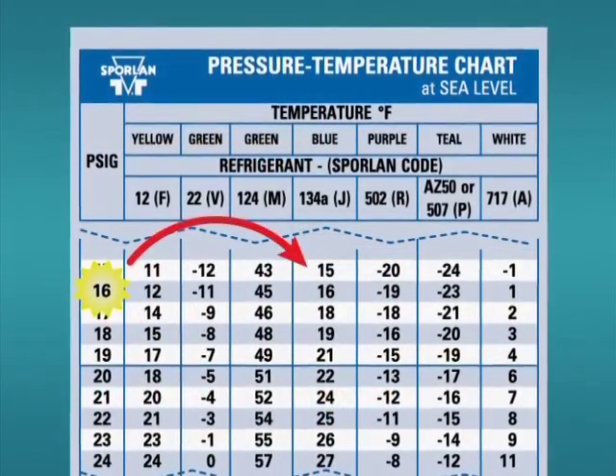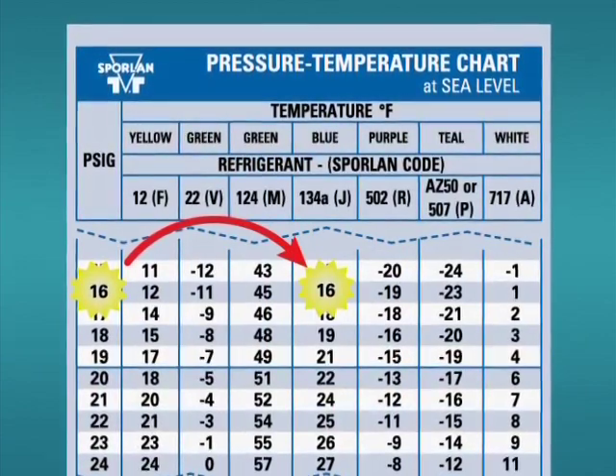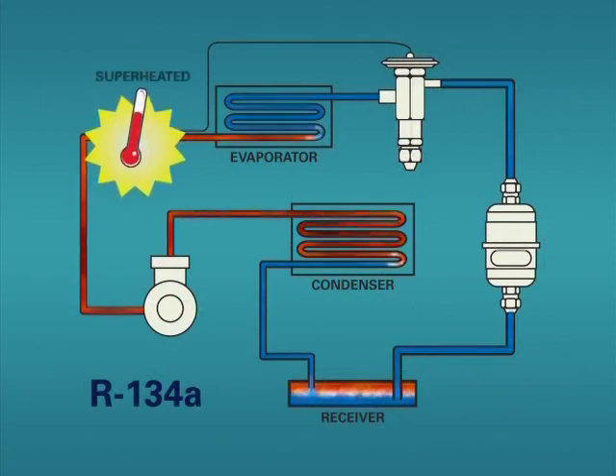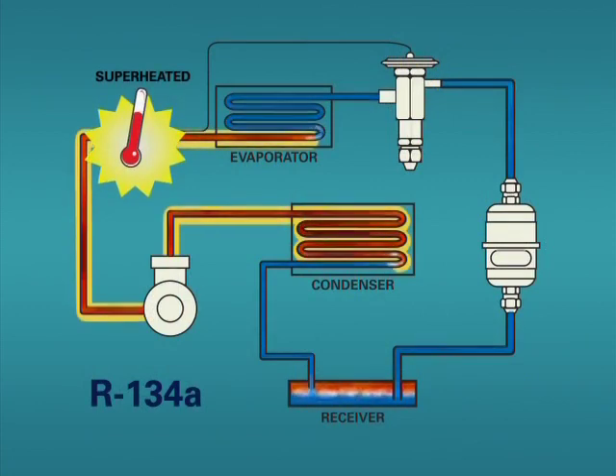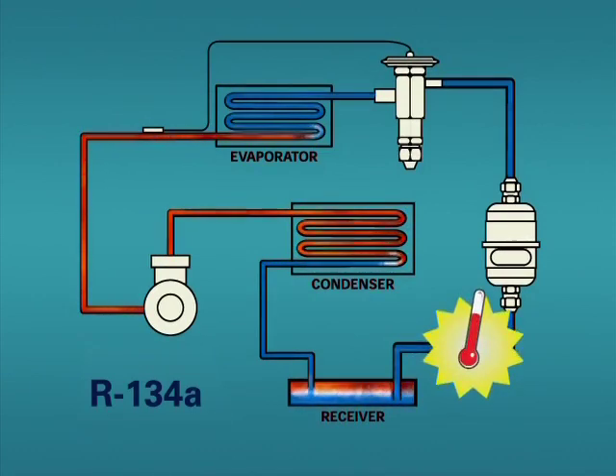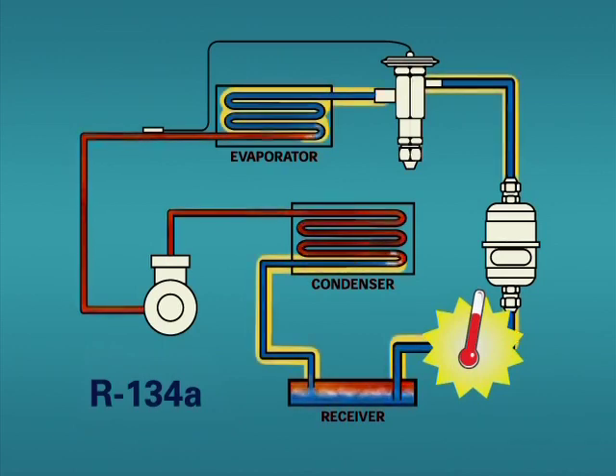This is true anywhere in the system, not just the evaporator, condenser and receiver. At points in the system where only vapor is present, the actual vapor temperature will be at or above the temperature indicated on the PT card. Vapor will only be present in the suction and discharge lines with a normally operating system. Where we have only liquid present, the actual liquid temperature will be at or below the temperature indicated on the PT card. Liquid refrigerant will be present in the liquid line which connects the condenser and evaporator coils.